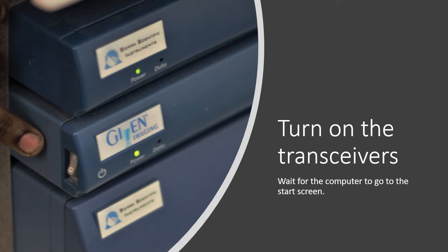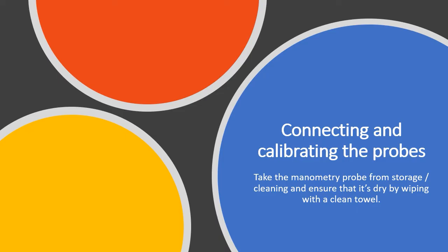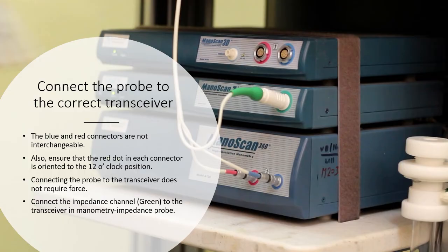After turning on the transceivers, wait for the computer to go to the start screen. Get the manometry probes from storage or cleaning and ensure that it's dry by wiping with a clean towel. When connecting the probes to the correct transceivers, remember that the blue and red connectors are not interchangeable. Also, ensure that the red dot in each connector is oriented to the 12 o'clock position. Connecting the probes to the transceivers does not require force.